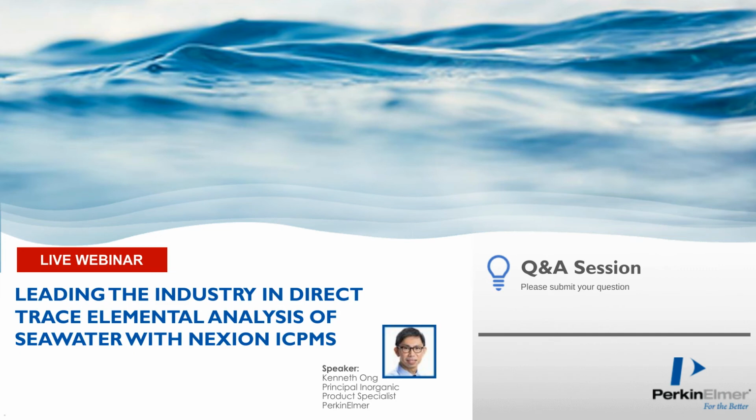So you must have a system that is able to take care of salt buildup such that it does not clog your orifice. The NexIONs, as we mentioned, have a wide orifice. So that will help to prevent the orifice from clogging up and causing signal drift.